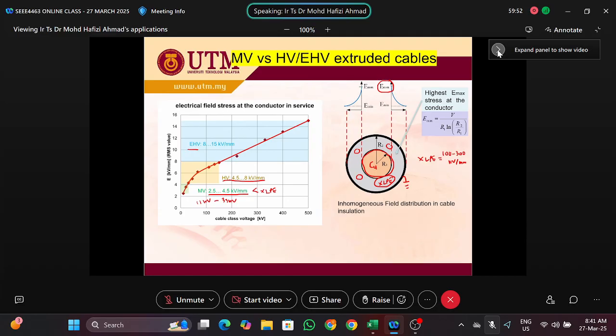Yeah, so this happens due to poor manufacturing process, due to degassing or vacuum process not being done correctly, and some air pockets may be trapped inside the XLPE. So because this is air, right? We know that air's dielectric strength is around 2.4 or 3 kV per millimeter, right? Yeah, but then you might see that the field strength at the surface of this conductor will vary within this. And of course, this value might exceed the breakdown strength of the air. And then what happens? A discharge may start to happen. And this is called electrical tree.